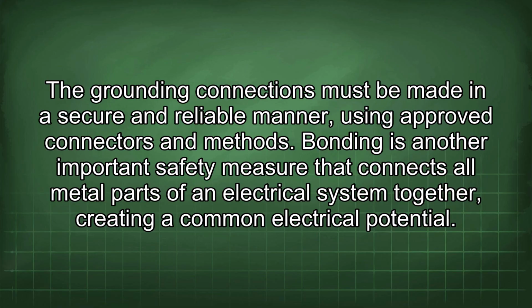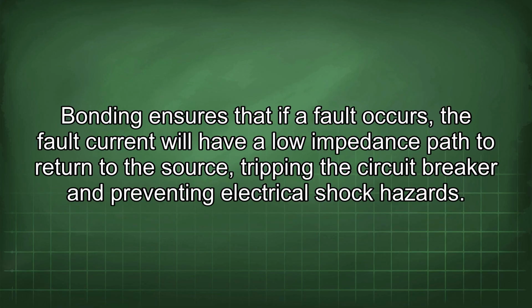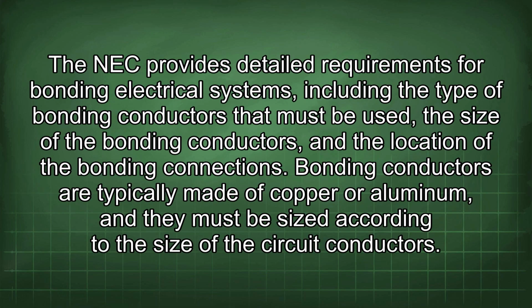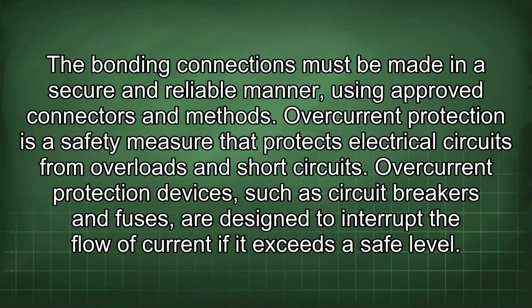Bonding is another important safety measure that connects all metal parts of an electrical system together, creating a common electrical potential. Bonding ensures that if a fault occurs, the fault current will have a low impedance path to return to the source, tripping the circuit breaker and preventing electrical shock hazards. The NEC provides detailed requirements for bonding electrical systems, including the type of bonding conductors that must be used, the size of the bonding conductors, and the location of the bonding connections. Bonding conductors are typically made of copper or aluminum, and they must be sized according to the size of the circuit conductors. The bonding connections must be made in a secure and reliable manner, using approved connectors and methods.